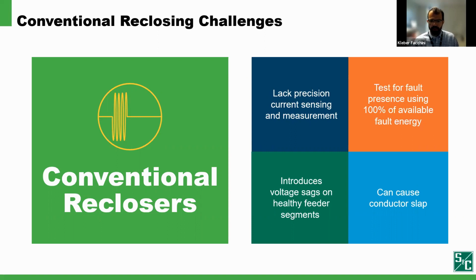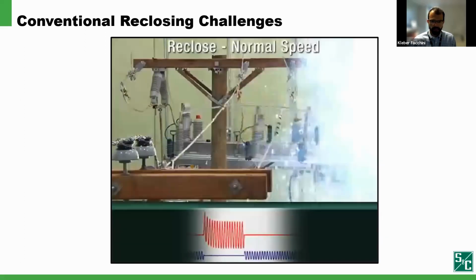Repeated reclosing can also cause conductors to slap, multiplying the problem by creating more faults upstream of the recloser that tripped to clear the initial fault. All of these byproducts of conventional reclosing can cause catastrophic damage to equipment and conductors, as well as decreasing reliability. I'll show you visually what I mean by testing for fault presence using 100% available fault energy, and the stress that is caused by it.